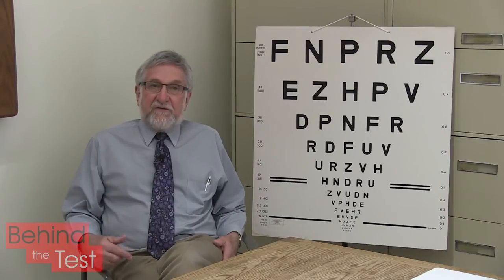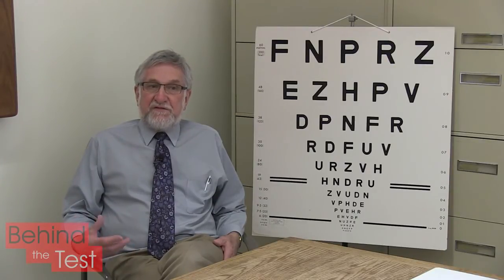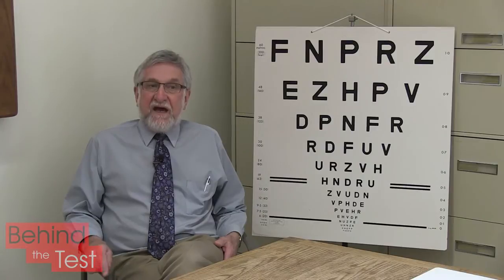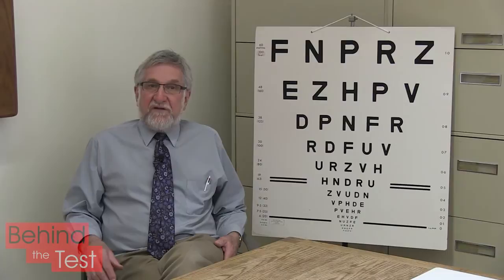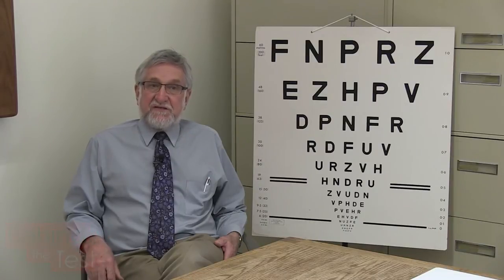Another feature of the charts is that as you go from one size level to the next, there's a constant ratio of size. When you put this combination of features together — that is, the same number of letters per row, proportional spacing, and a constant ratio of size — you end up with a chart where the task is the same at each size level.